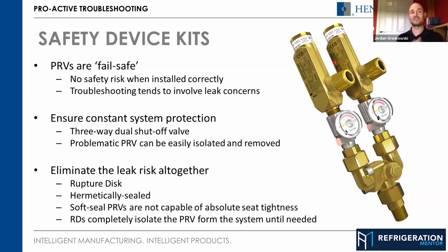So those are the two things. Your 3-way valve allows you to maintain valves and switch valves out really easily. And your rupture disc gives you that. It's the only solution that will give you complete leak tightness and give you that peace of mind that there's no weep occurring anywhere in the system.